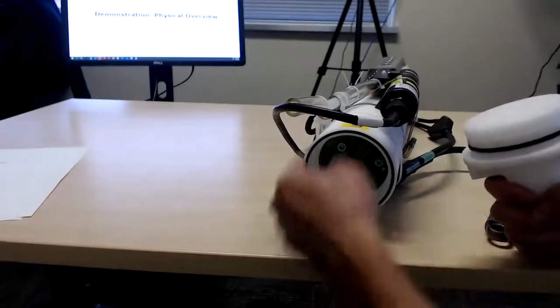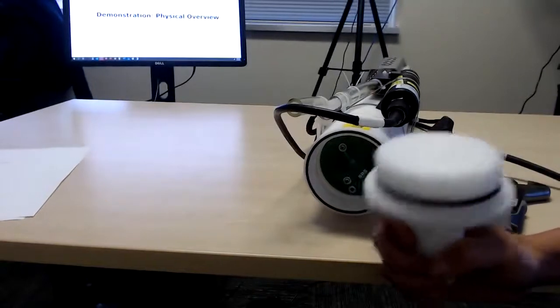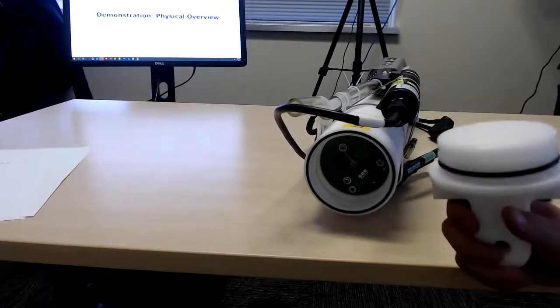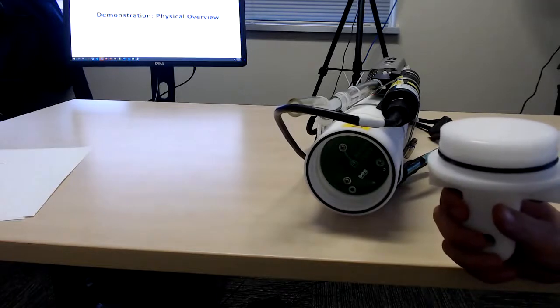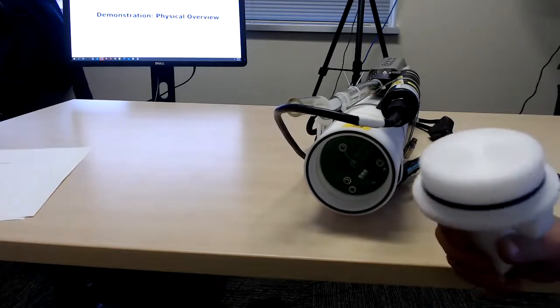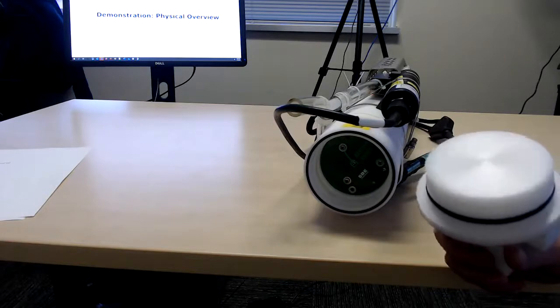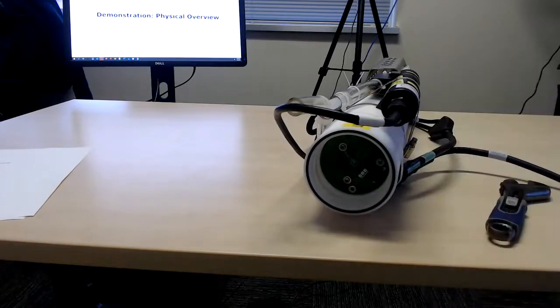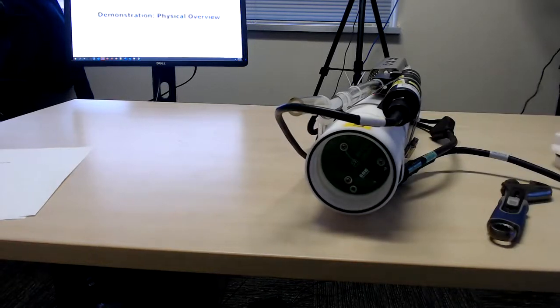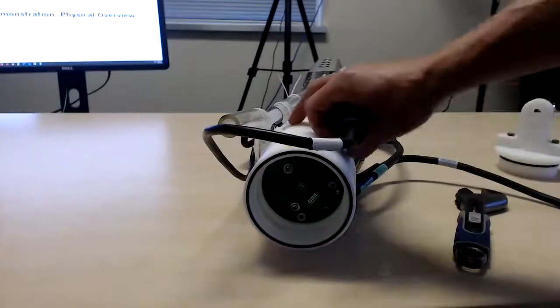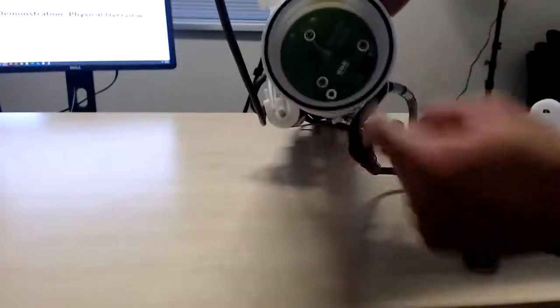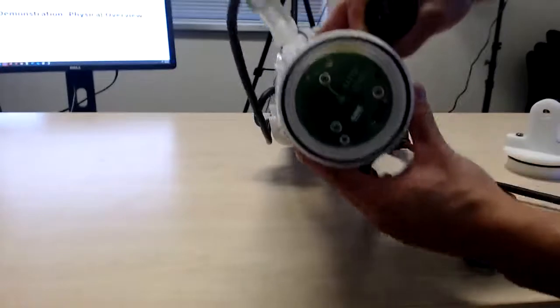Okay, a couple of things here. We have an O-ring right here and an O-ring on the end cap here. This is obviously a pathway for flooding, so it's very important that these O-rings are in good condition, that they don't have any fibers bridging them, and that you take good care of them and inspect them before you reinstall the end cap on the CTD. Setting that aside, the next thing we see is this battery cover plate, this little green thing.